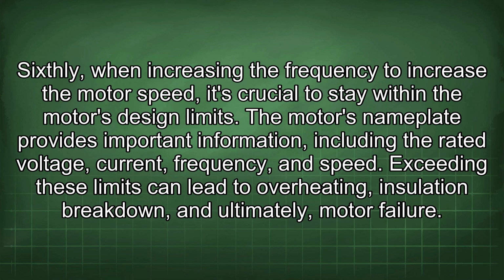Sixthly, when increasing the frequency to increase the motor speed, it's crucial to stay within the motor's design limits. The motor's nameplate provides important information, including the rated voltage, current, frequency, and speed. Exceeding these limits can lead to overheating, insulation breakdown, and ultimately, motor failure.